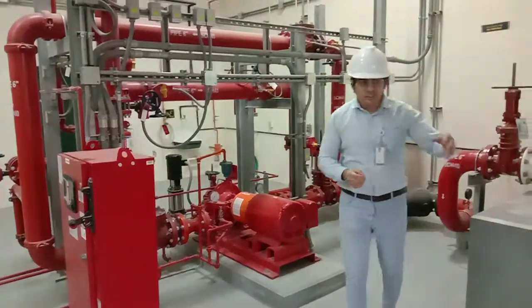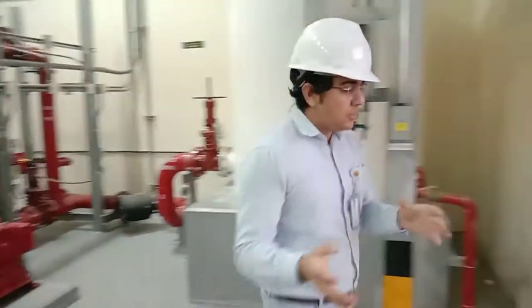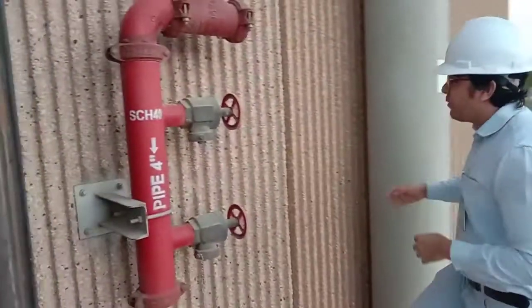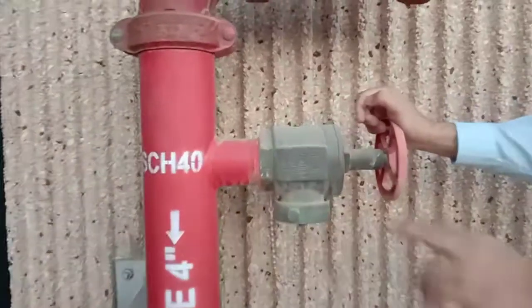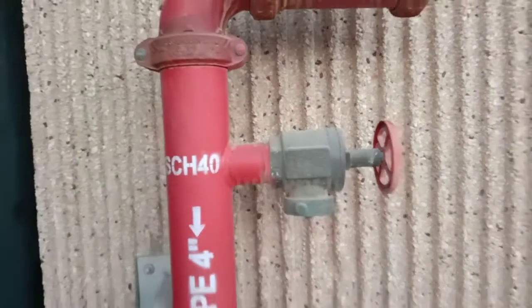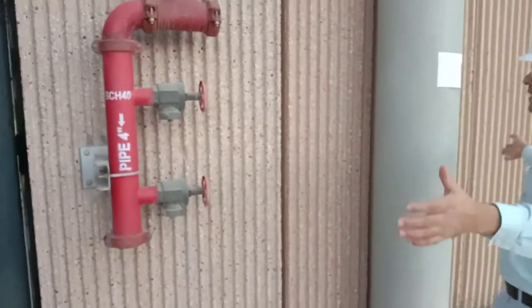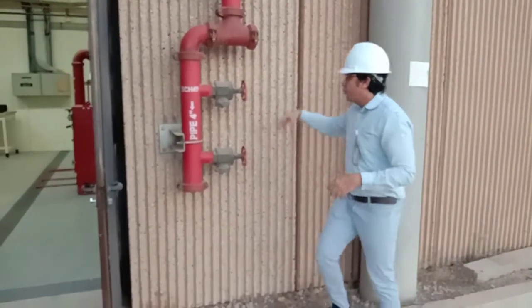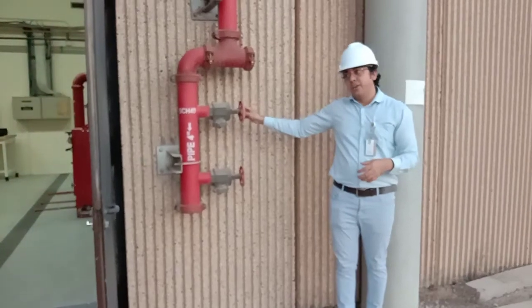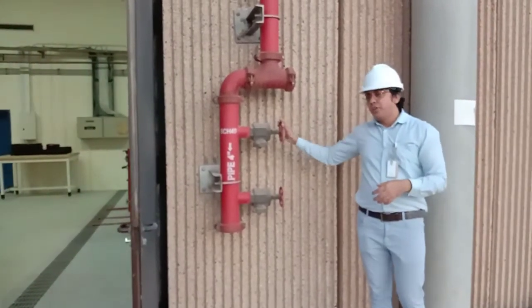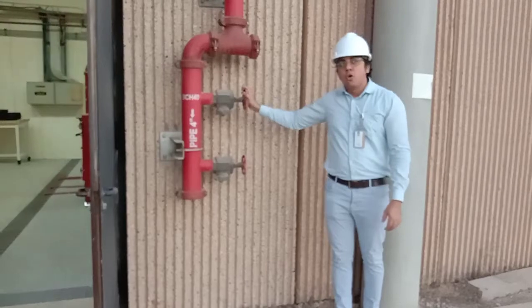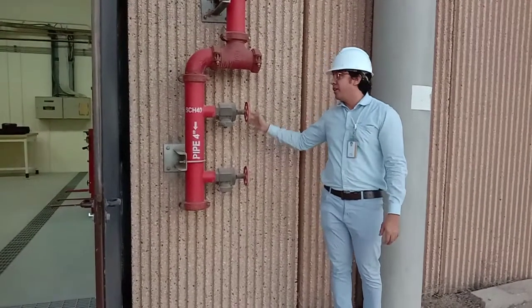Let's start from the test header, which is outside in our campus, because this is the most common one we can see at most places in a fire protection system. So we normally have a 2.5 inch test header, right? These are 2.5 inch and UL listed. It might be 2, it might be 4, based on the size of the pump. Or there might be a test header with 6 connections. You can find this as per NFPA 20, the latest table 4.27 or something. I don't remember exactly. It will tell you, based on the capacity of the pump, what the size of the test header should be and what the number of test headers should be.